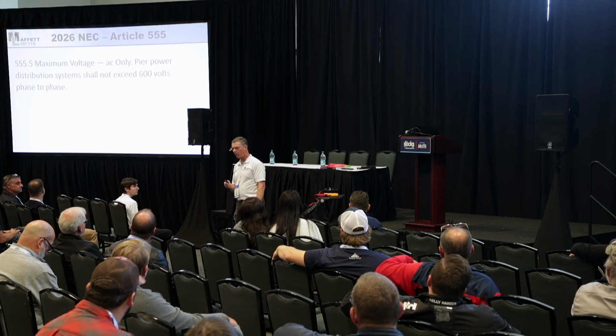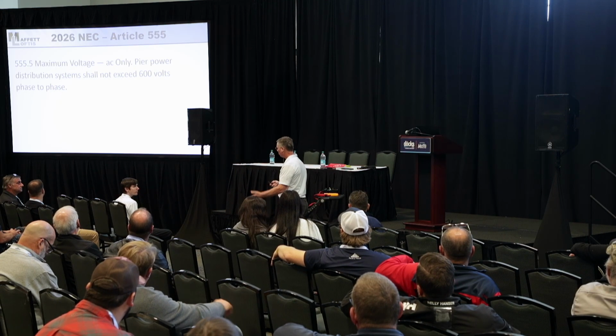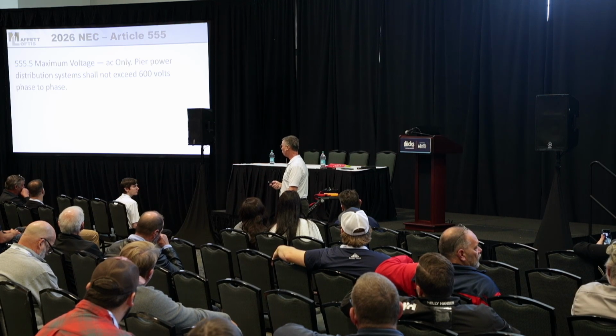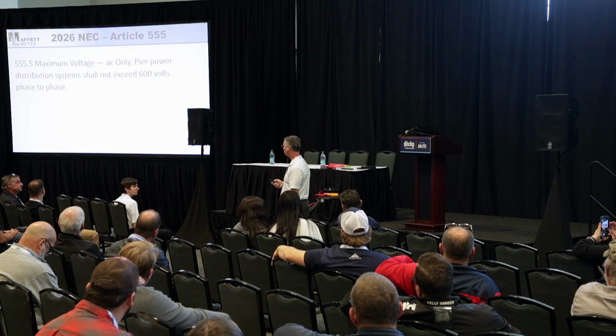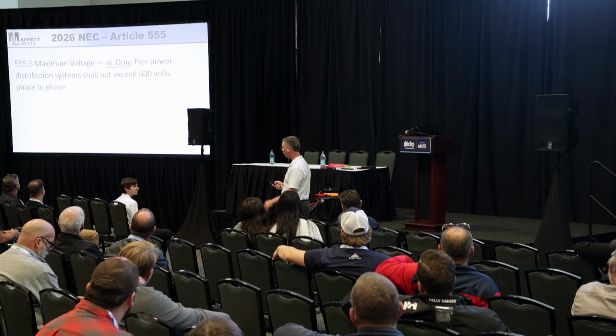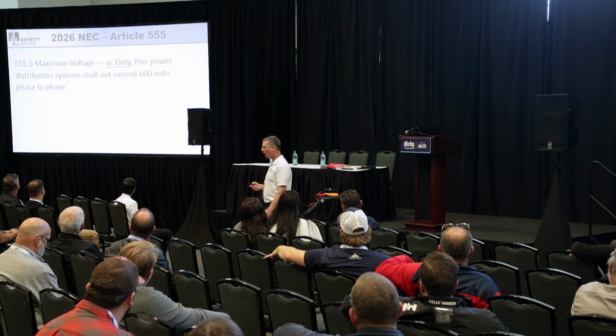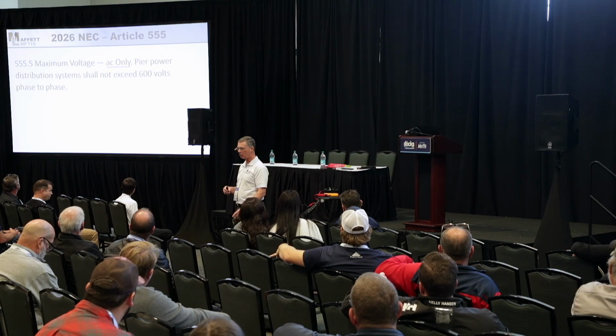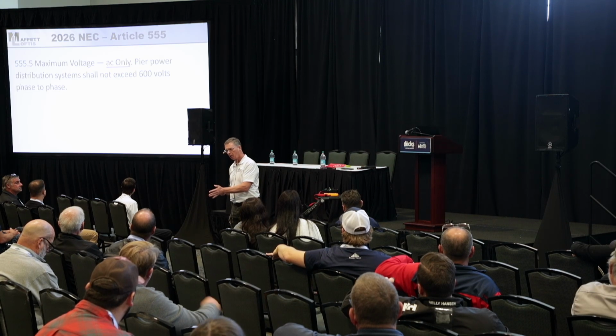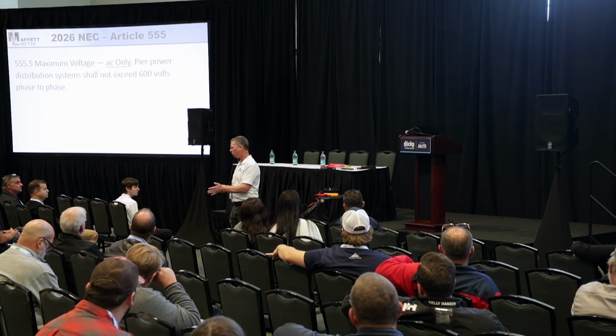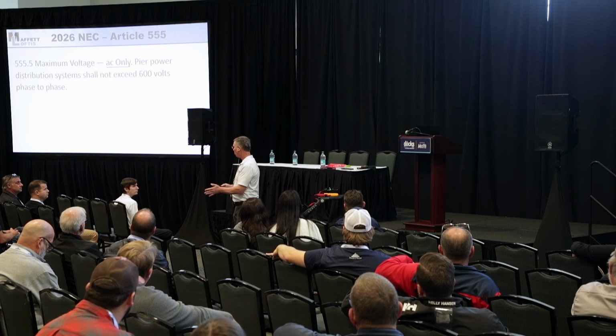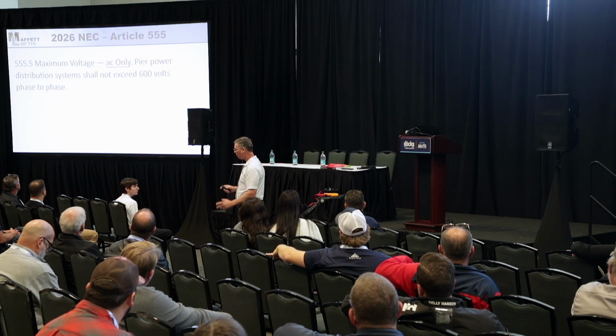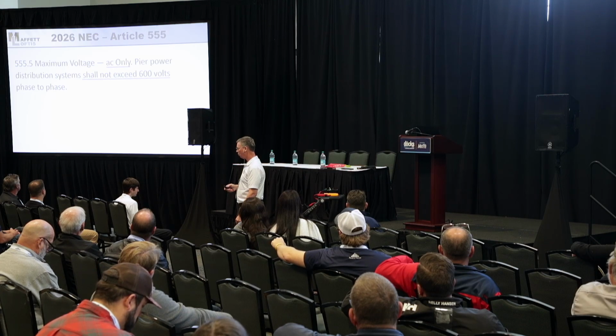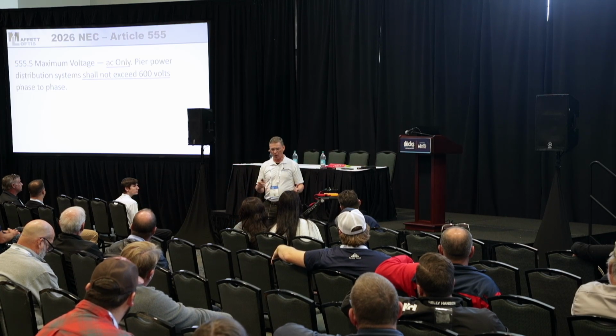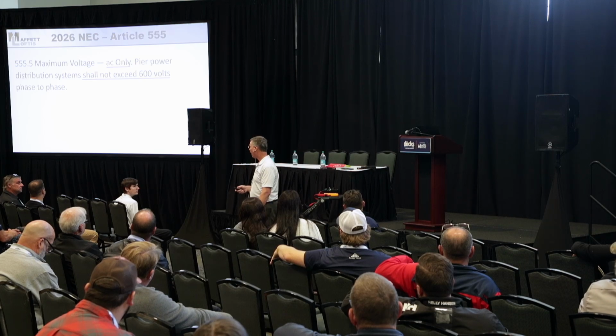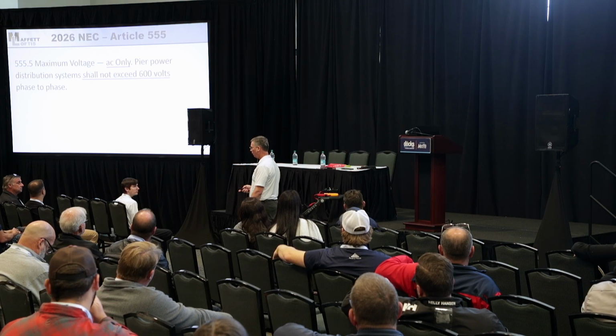I want to talk about maximum voltage, because we changed the code here from 2023 to 2026, and now they're making us put AC only in. Every time we refer to a voltage, it has to be AC, because we're getting a lot of DC equipment on docks now, especially DC charging systems. So when we say this, we're only referring to an AC system for a maximum of 600 volts. We're not regulating a DC voltage level with Article 555.5.